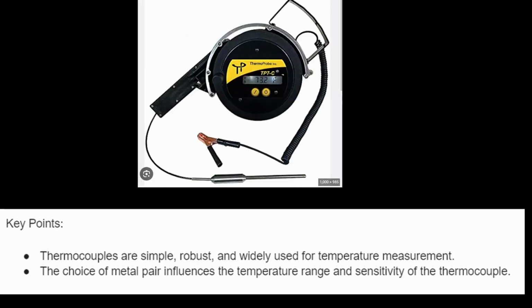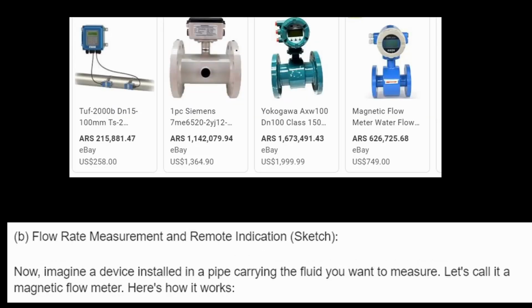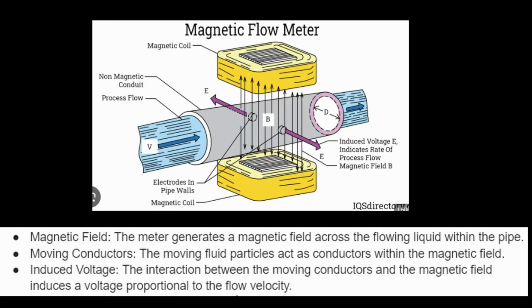Key points. Thermocouples are simple, robust, and widely used for temperature measurement. The choice of metal pair influences the temperature range and sensitivity of the thermocouple. B. Flow rate measurement and remote indication with sketch. Now, imagine a device installed in a pipe carrying the fluid you want to measure. Let's call it a magnetic flow meter. Here's how it works. Let's look at the sketch.